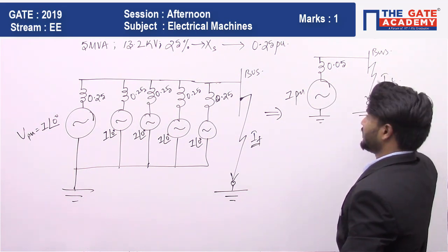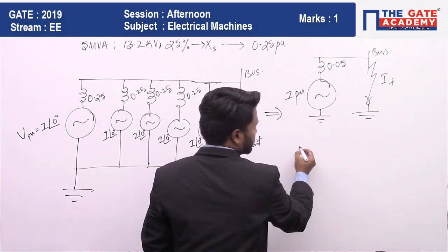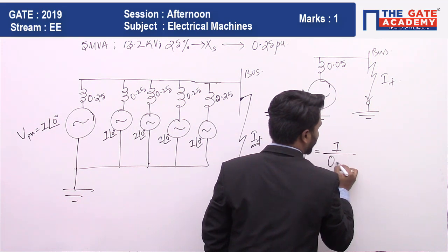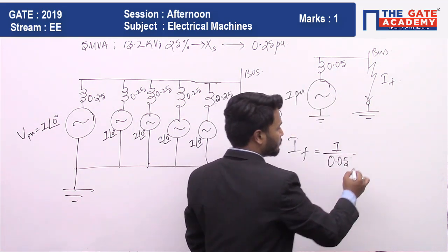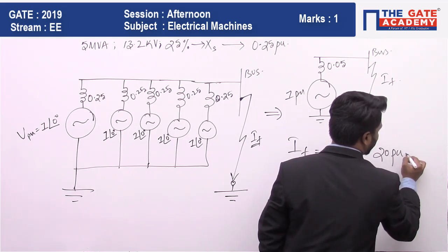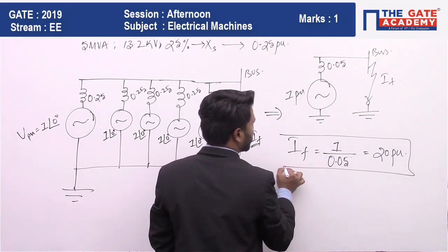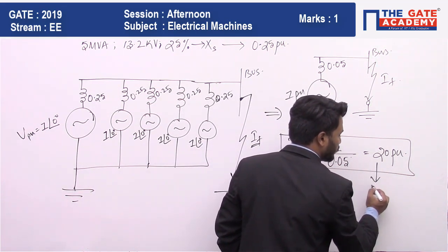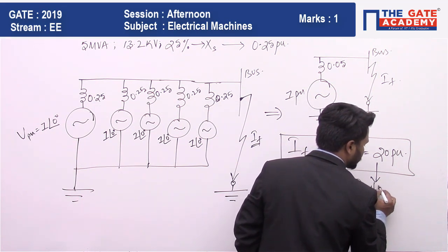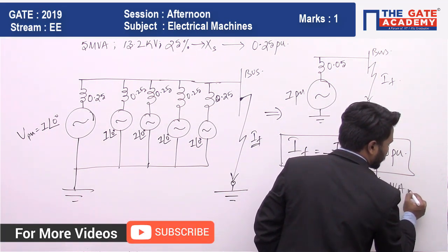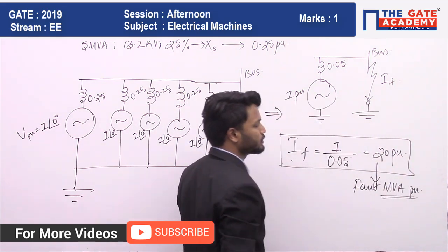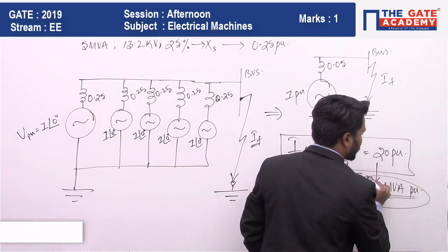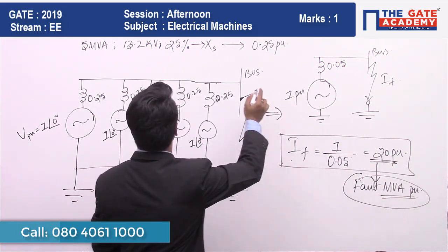The fault current I_f equals one per unit divided by 0.05, which gives 20 per unit. The fault current in per unit equals the fault MVA in per unit — this is a standard relation: fault current per unit is equal to fault MVA per unit.